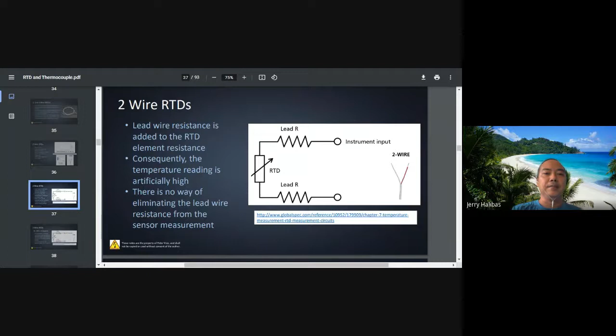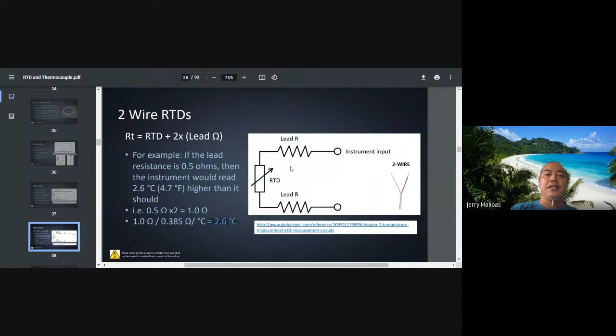Okay, so we can consider that because there is resistance in your wires, let's say 0.5 ohms on both sides, so times 2 that's an additional 1 ohm plus the resistance of your RTD. That's around 1 degree or more of error. So the effect is you add, not really, it's supposed to be 1 degree, but the reading of resistance is affected because of the lead wires or extension wires.